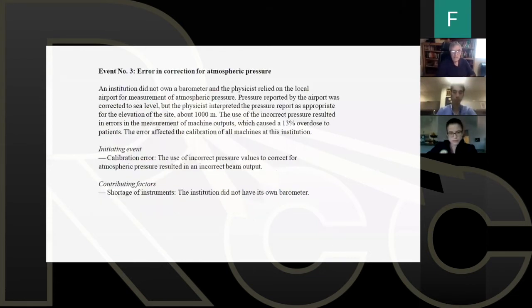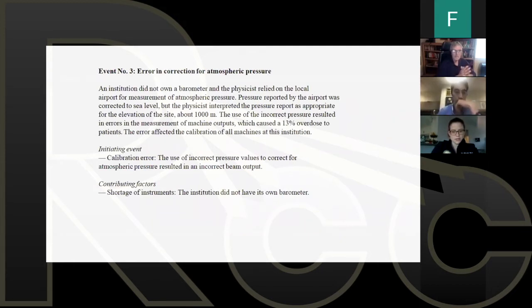A third error that can be quite common throughout the world because of the different geographical heights that we operate at. Some of us work at sea level, some of us work at some very high altitudes, and serious errors have happened because of wrong barometric pressure readings. Here's a situation that the physicist relied on the local airport. Many times physicists will call the airport for a barometric pressure to correct their vented ionization chamber. This is a dangerous thing to do unless the physicist clearly understands how the airport is reporting barometric pressure.